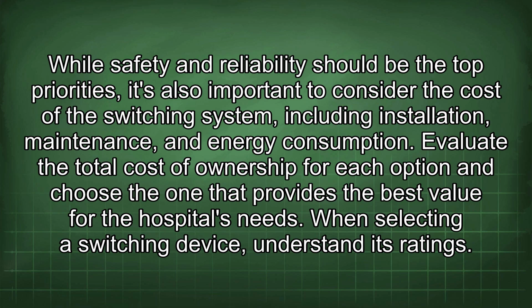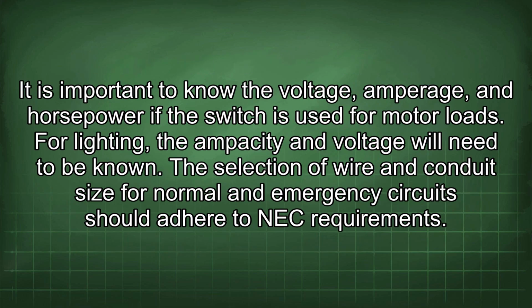device, understand its ratings. It is important to know the voltage, amperage, and horsepower if the switch is used for motor loads. For lighting, the ampacity and voltage will need to be known. The selection of wire and conduit size for normal and emergency circuits should adhere to NEC requirements.